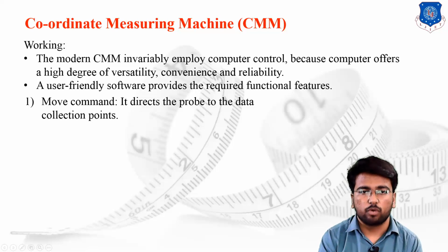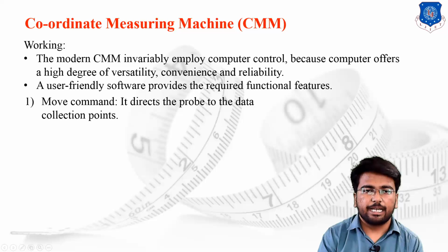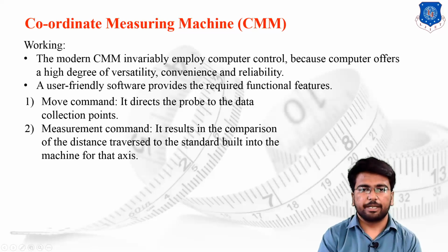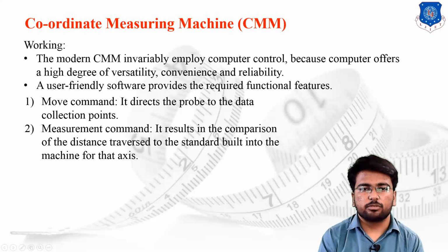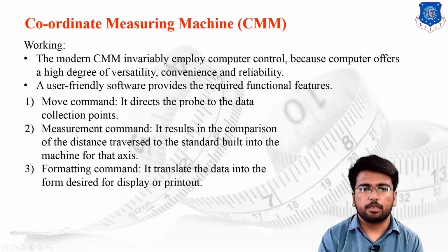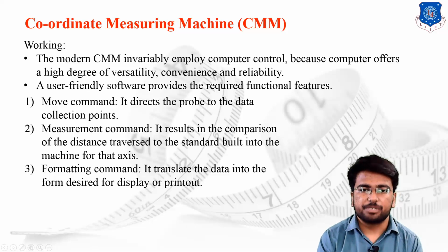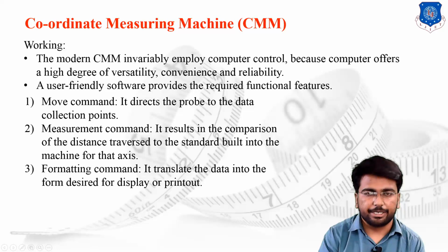The basic commands provided by the software for the CMM are as follows. The first one is the move command, which directs the probe to the data collection point. Then the measurement command, which results in the comparison of the distance traversed to the standard built into the machine for that axis. And the last one is the formatting command, which translates the data into the form desired for the display or printout.